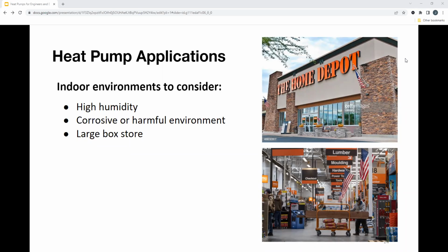A way around that too, I'm going to talk about this a little bit later on in special applications, is that there is a solution where you are able to take a third-party DX coil in a rooftop unit and connect a heat pump to that to control cooling and heating, right? So you're not installing heat pump fan coil units in these large spaces just because there's not a lot of stratification and airflow. Can't really meet those requirements with a heat pump, but you can with rooftop units and still utilize the heat pumps to provide that cooling and heating. So just something to look out for as you're designing systems. There are always solutions out there, so please ask as you're selecting products.